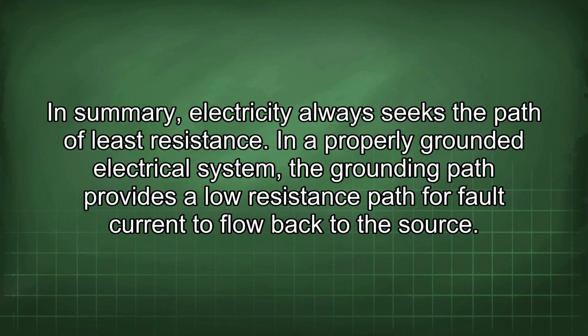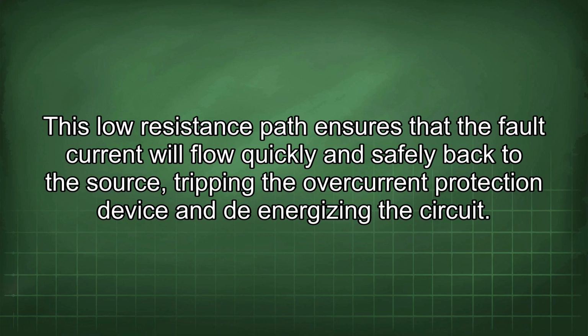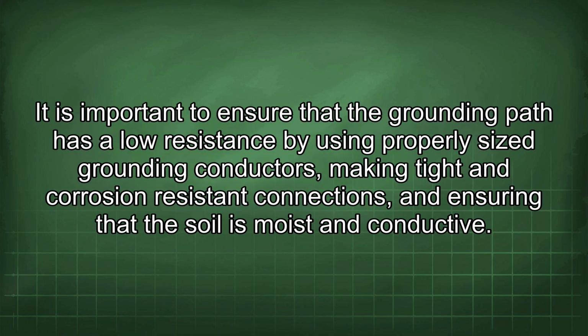In a properly grounded electrical system, the grounding path provides a low resistance path for fault current to flow back to the source. This low resistance path ensures that the fault current will flow quickly and safely back to the source, tripping the overcurrent protection device and de-energizing the circuit. It is important to ensure that the grounding path has a low resistance by using properly sized grounding conductors, making tight and corrosion-resistant connections, and ensuring that the soil is moist and conductive.